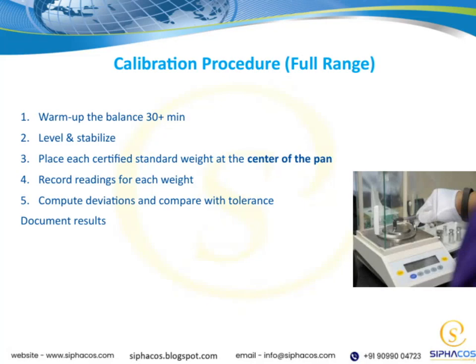All right, let's walk through the calibration procedure for the full range of the balance. First, it's essential to warm up the balance for at least 30 minutes. This warm-up helps ensure the instrument reaches a stable operating temperature, which is crucial for accurate measurements. Once warmed up, you need to level and stabilize the balance. Proper leveling prevents any tilt that could skew the readings and guarantees consistent results throughout the calibration.